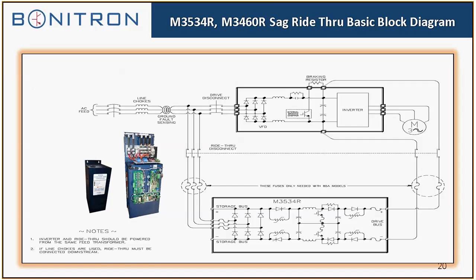Okay, this shows the M3534R connected to a variable frequency drive. As you can see, there are AC line connections, and those are in front of the drive. They can connect to the drive terminals, or they can connect up in front of the drive. There is a ride-through disconnect that's included with the cabinet systems. This is a very important component because this disconnects the whole ride-through system from the drive. So when you're doing maintenance and you want to lock out, tag out something, that would be the disconnect that you would lock out.